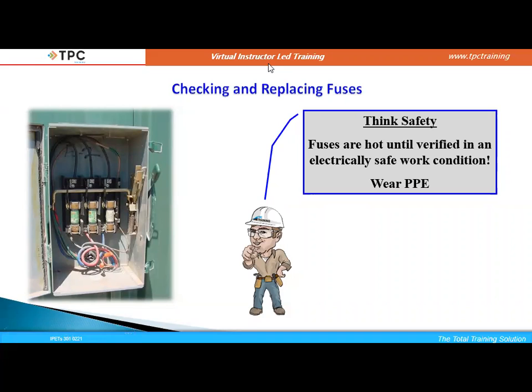One important thing here I do want to reiterate. When I install these fuses back in this fuse disconnect, I want to make sure they're turned so that I can read the information, because all three of those fuses, they better be identical. Let's say that we have a three-phase motor. That three-phase motor has identical windings in it, and so I need identical fuses here.